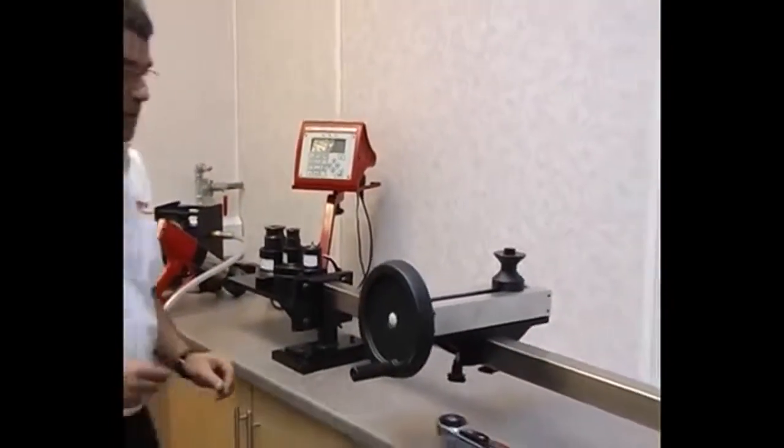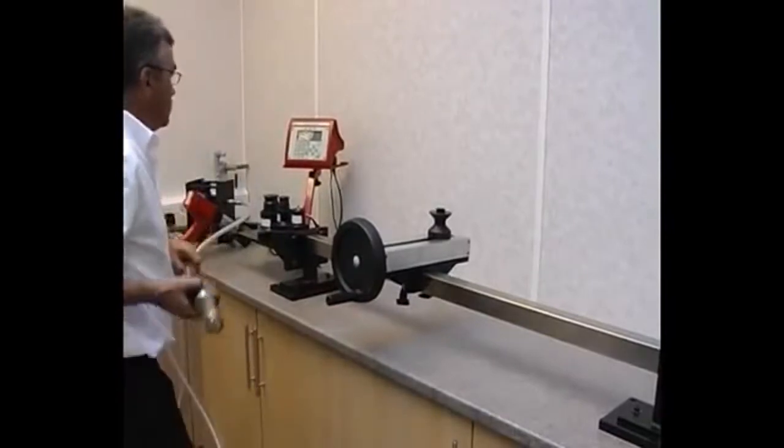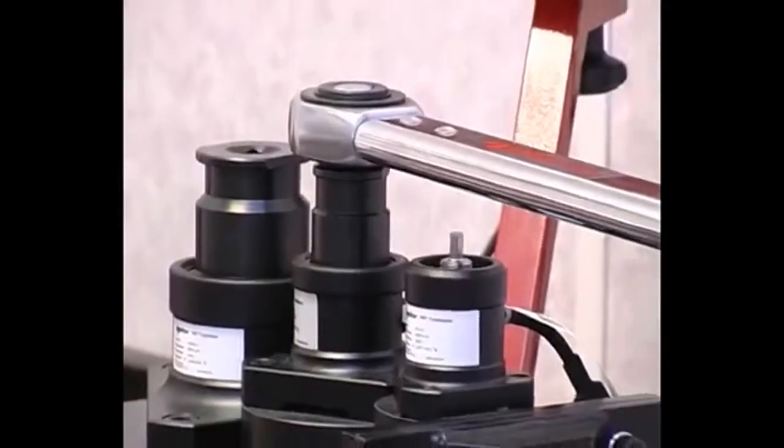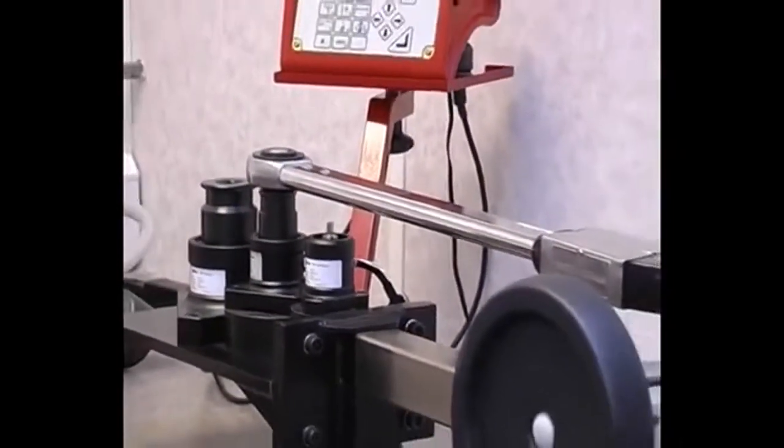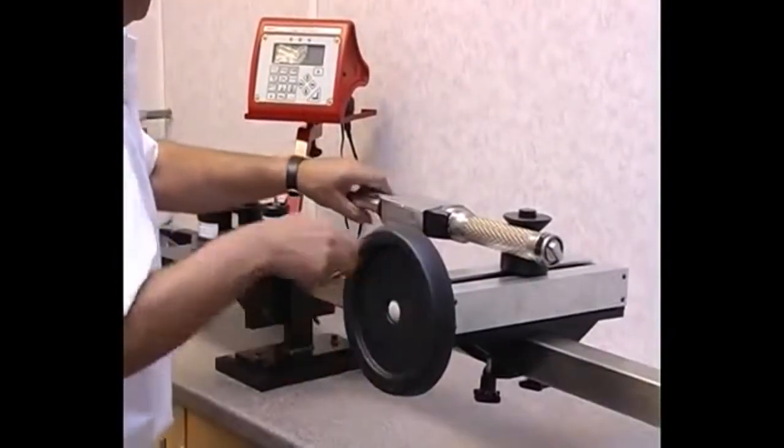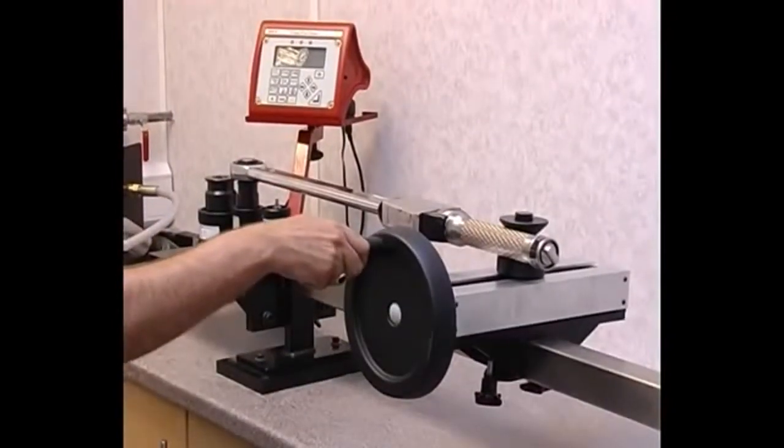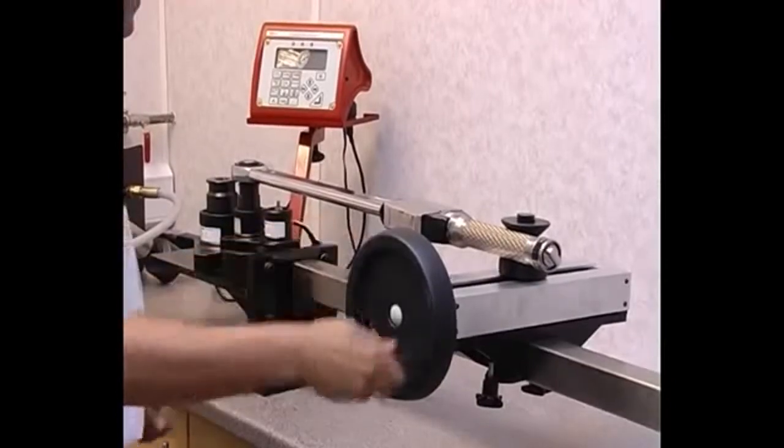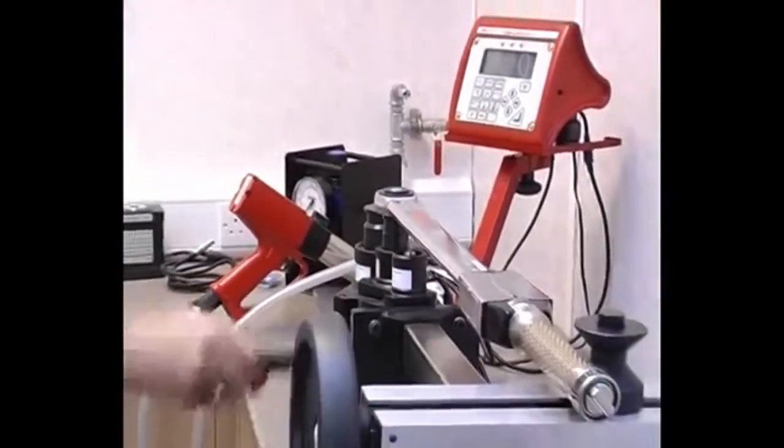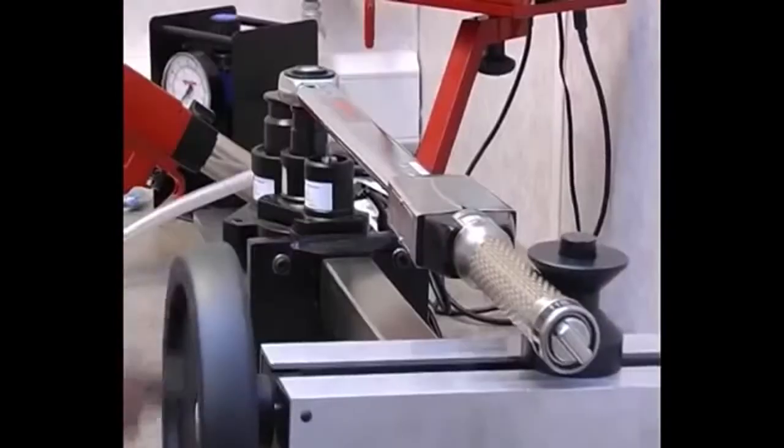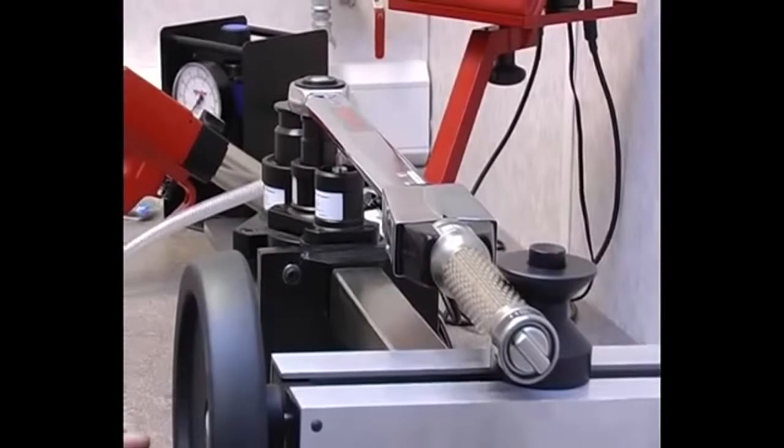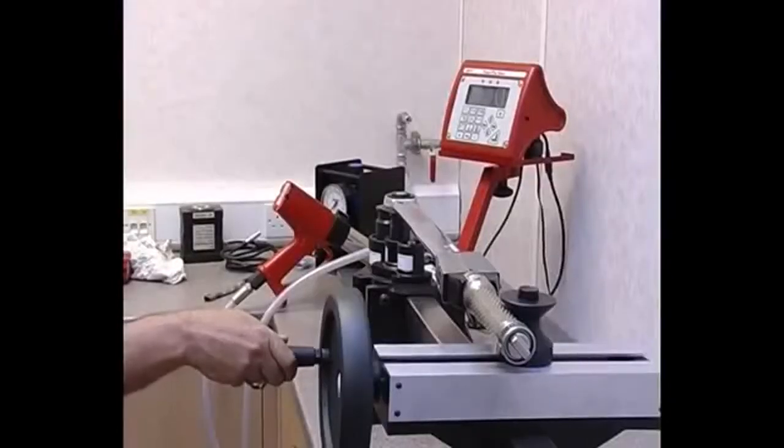The TWL1500 is an accurate and cost effective loading rig for calibrating torque wrenches between 1 and 1500 Nm. Large torque wrenches can be operated effortlessly by simply winding the handle, while the TTT captures the first peak of torque in the case of click type torque wrenches.